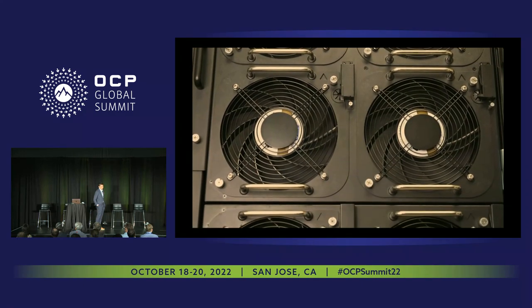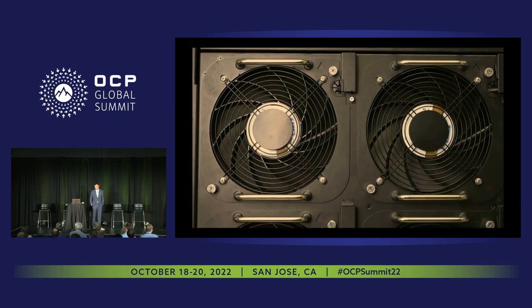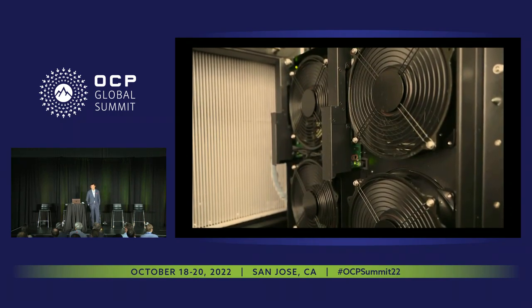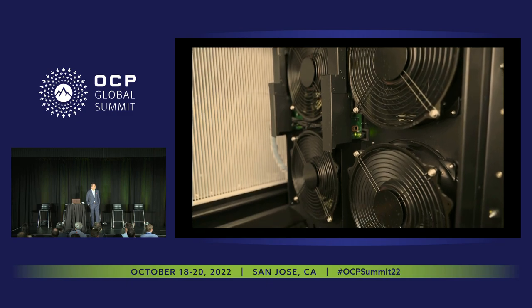For the fan zones, the CDU manages each node's workload to zone 16 fans into 2 to 4 fan groups to balance the coolant's temperature and decrease power consumption.